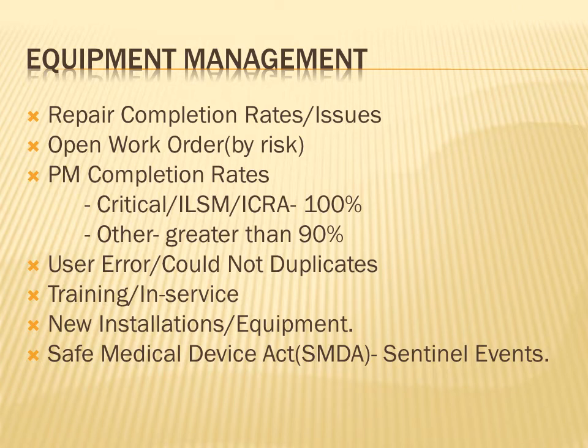It's one of those things where you definitely want to get it done as early in the month as possible, so that when you do your report, everything is done on the critical equipment. The other equipment, of course, is also very critical, and typically 90% completion rates are standard for being adequate. Some people go to 95%.